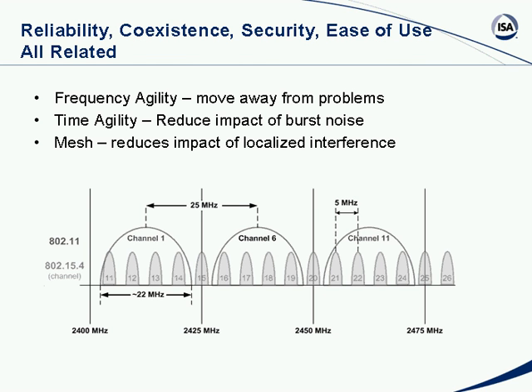The availability of frequency agility is important — if one channel has a problem, either an interferer or a multipath null, the channel can be changed and the problem avoided. In our approach to the MAC layer, ISA 100.11a offers the opportunity to move the slot around in time, which will reduce the impact of interference from burst noise or other potential interferers. It also offers the mesh we need, which reduces the impact of geographically local interference — you can route around an interferer. There's now a company that sells a product allowing you to map your Wi-Fi network around your microwave oven using a repeater to avoid that interference.